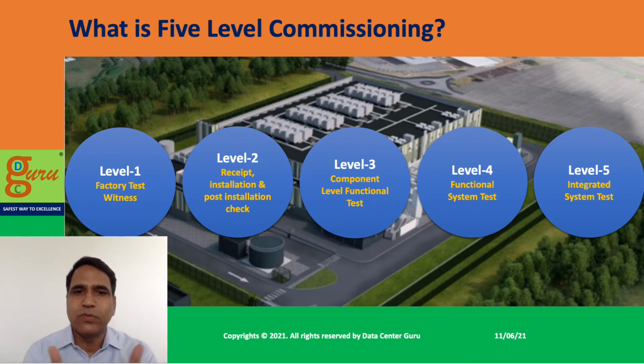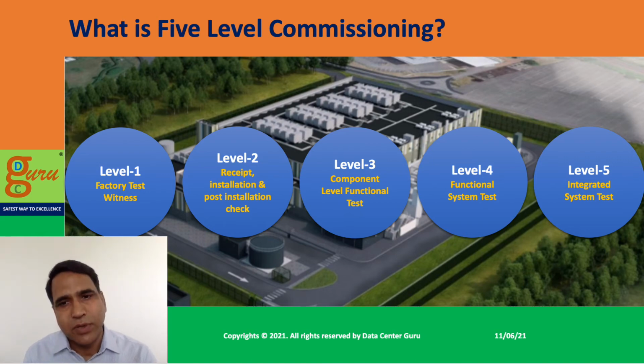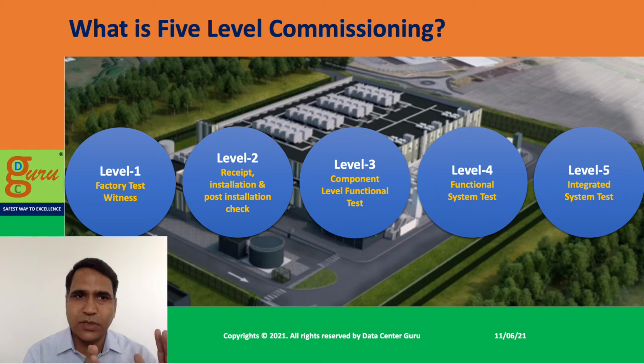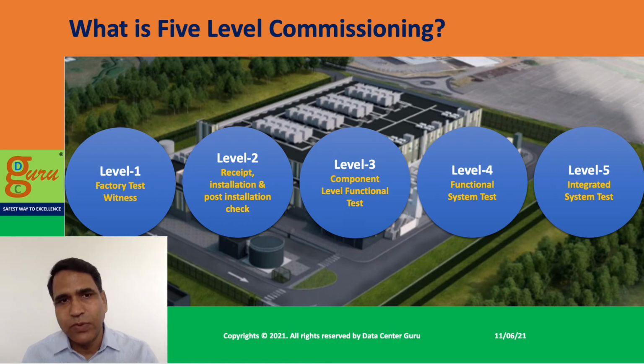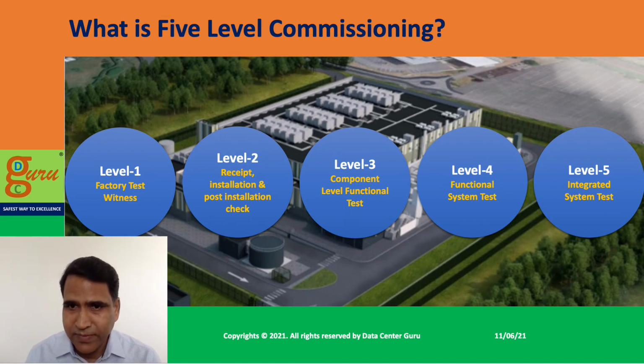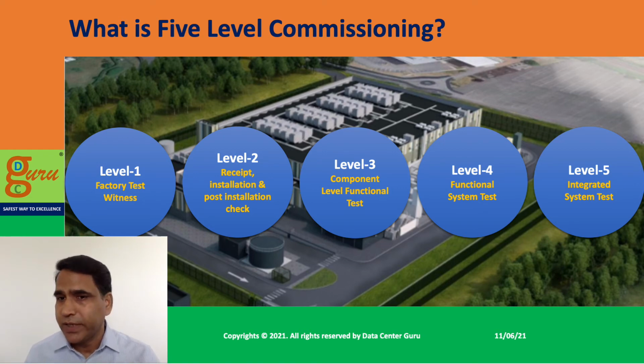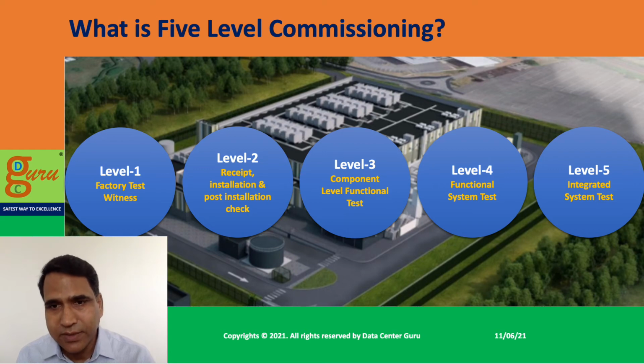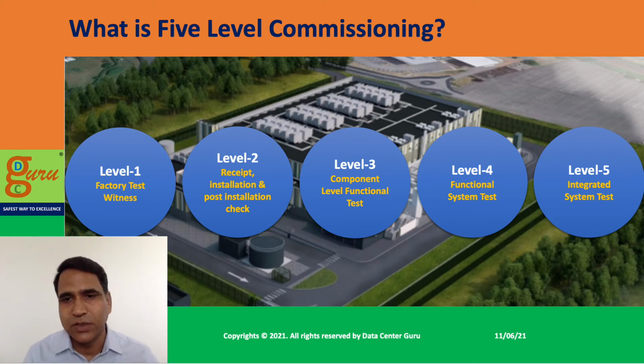Normally in the industry, what we observe is people call it ISAT or ISBT, which is level 5 commissioning - that's very popular and people go along with it and document it. But all the other levels of the commissioning process have a lot of gaps. It is not done religiously and in completeness to plug those gaps, and due to this, at level 5, when you start commissioning, you identify certain gaps which could have been identified at level 2 or level 1 itself. That's when it becomes very difficult, in fact not feasible, to plug those gaps, and you start living with it, which is not good, because you are compromising your outcome.